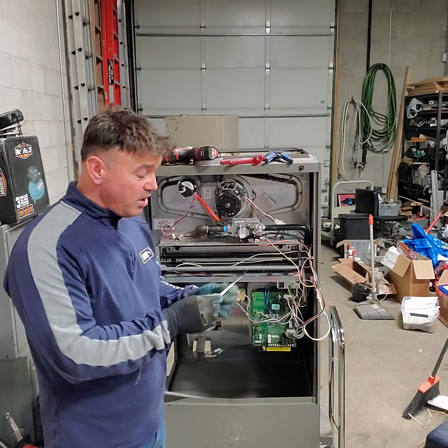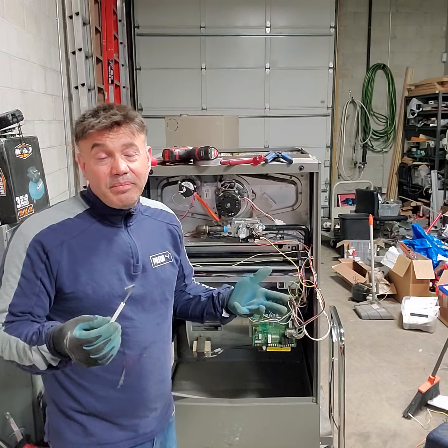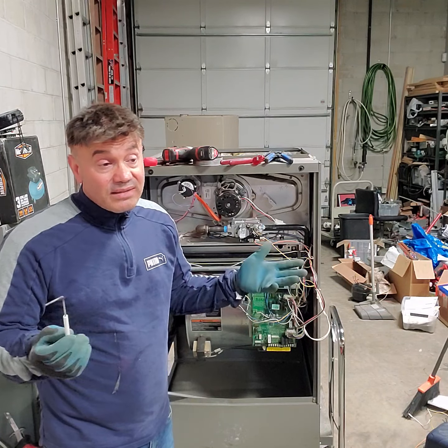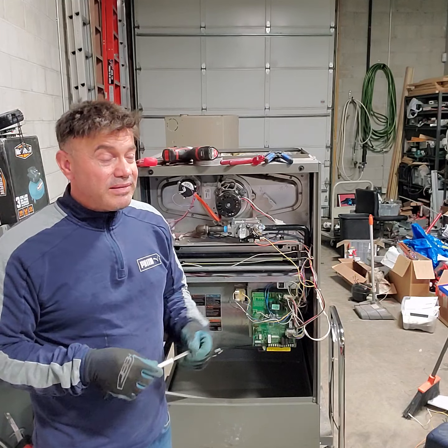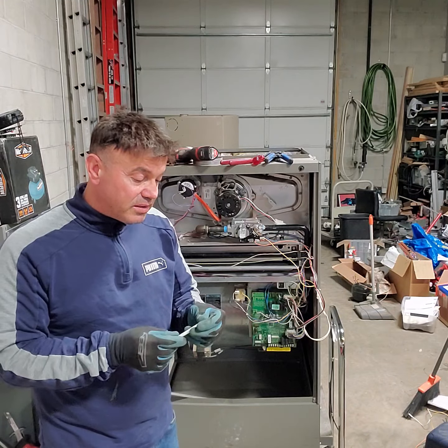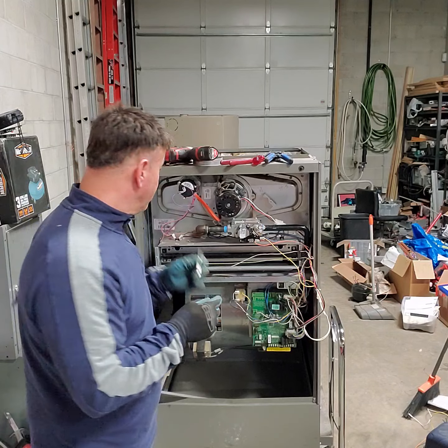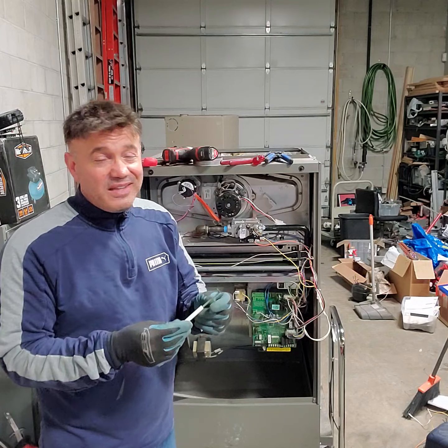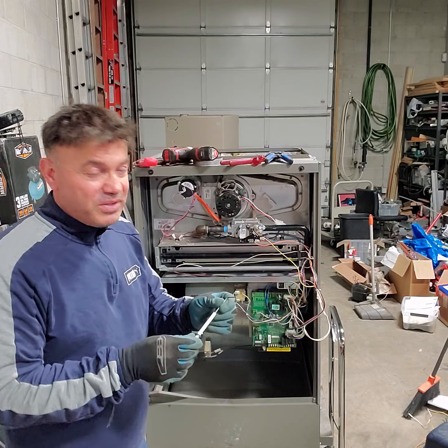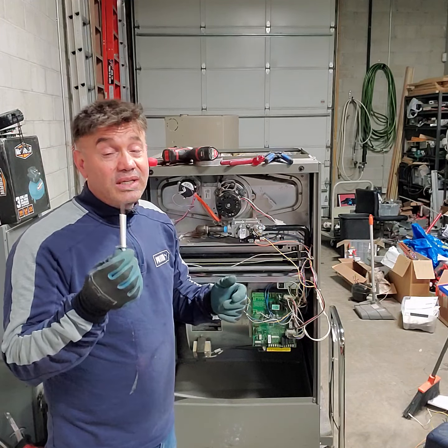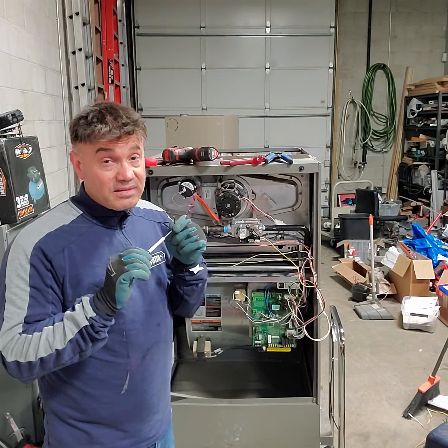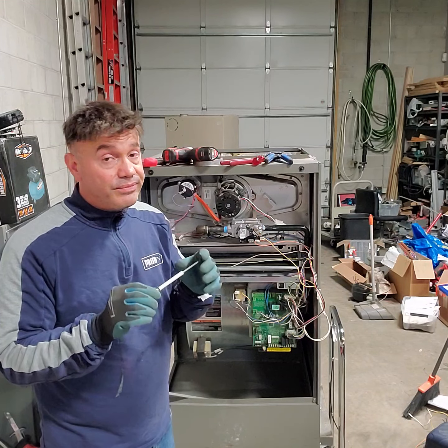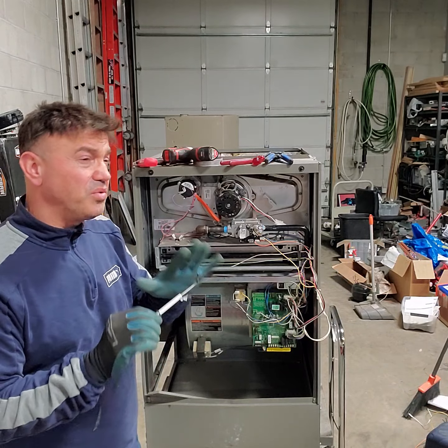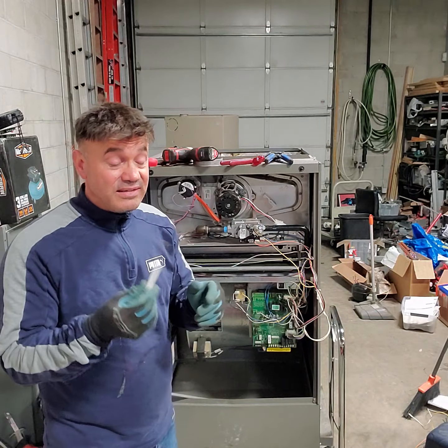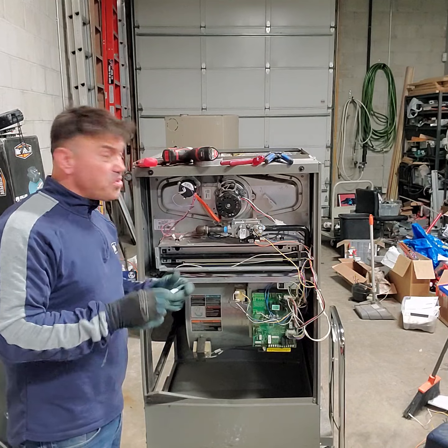So a lot of the time, in my case, I don't test it, even though there is a way to test it which I explained. I usually keep all kinds of sensors in my truck, and usually I just replace them, because you're not gonna go to a job, clean it, and put it back — what are you gonna charge them for? These flame sensors can range anywhere from $6 up to, for something like Lennox which is expensive, easily $40 to $80, and sometimes I've seen them over $100. So usually I just replace it.